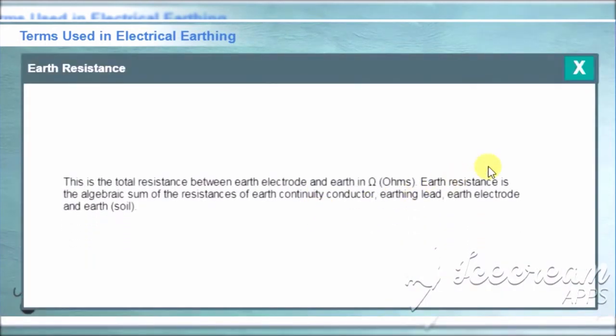Earth resistance. This is the total resistance between earth electrode and earth in ohms. Earth resistance is the algebraic sum of the resistances of earth continuity conductor, earthing lead, earth electrode, and earth or soil.